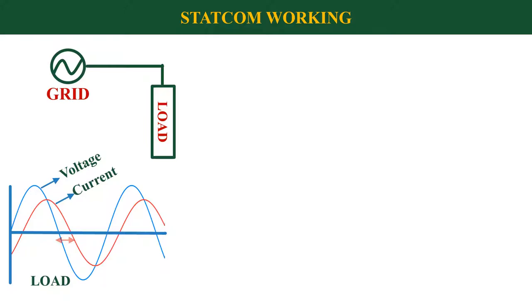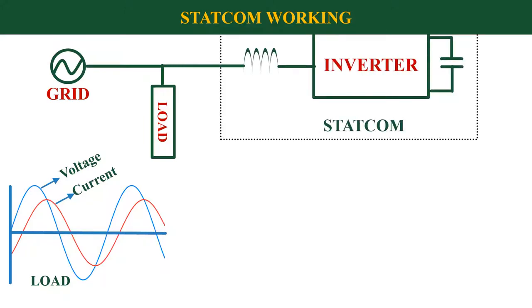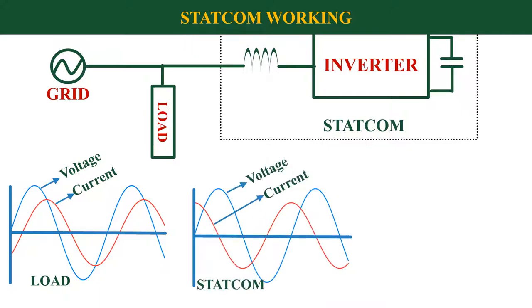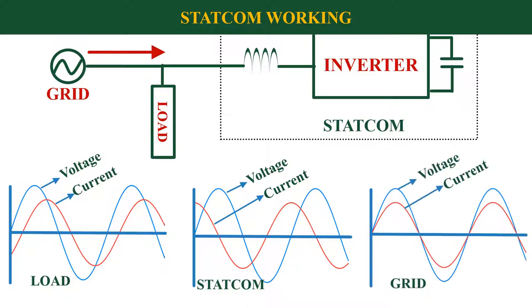Now we are connecting a Statcom at the same point where we connected the load. Assume that the Statcom is generating reactive power which is equal to the reactive power consumed by the load. But here the current leads the voltage by 90 degree. So when we inject reactive power to the grid, the net reactive power taken from the grid will become zero. So the grid power is now purely active in nature. This is how we control the reactive power in any network using Statcom.